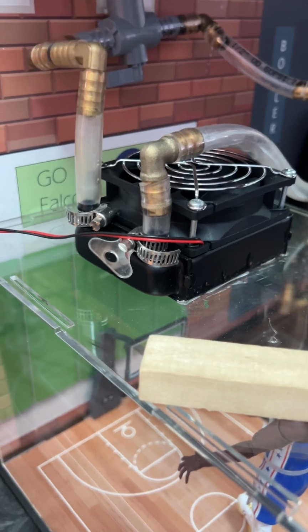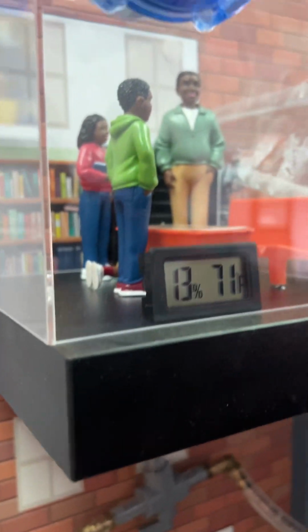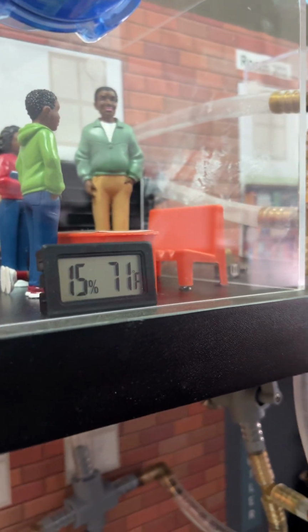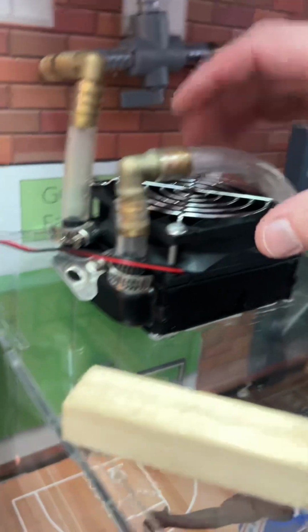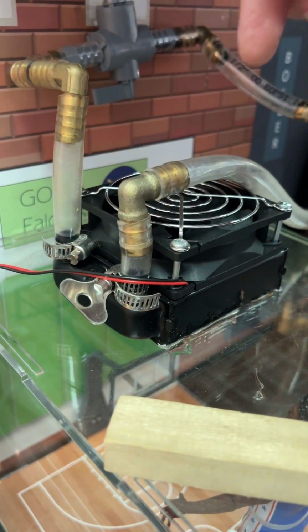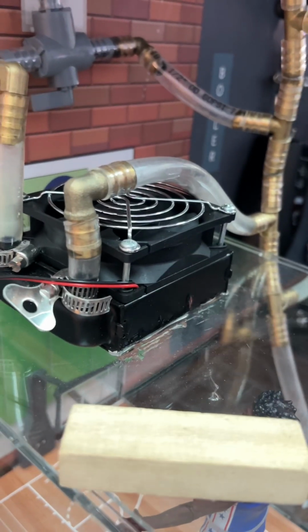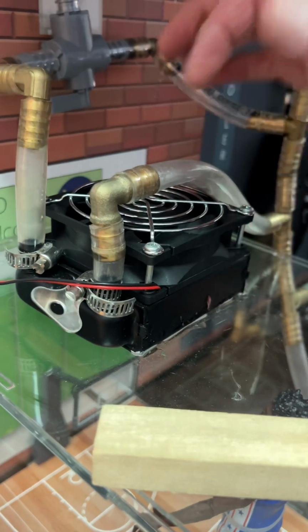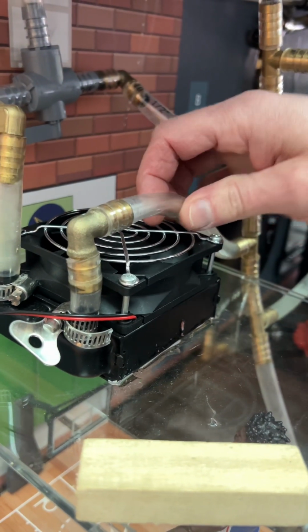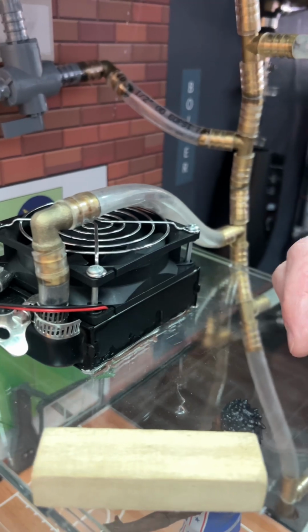The classroom shows something where the air blows in more or less at ground level, where it would be blowing through a unit vent through the wall, in the outside wall of the building, which you see in a lot of classrooms. Water circulates through these coils. This one's easier to see, so I'll point at the gym one. There's a fan here that blows air through the coil. The coil just looks like a radiator in a car, has water circulating through it. If there's hot water in it, as the air blows over, it blows warm air into the space. If there's cold water in it, chilled water, it will blow cold air into the space.